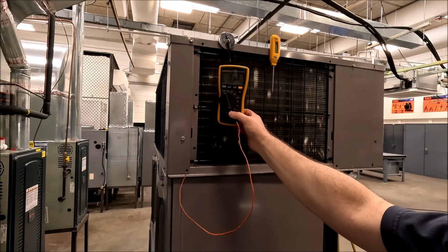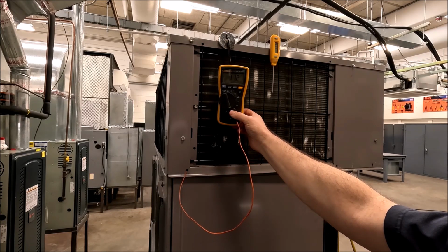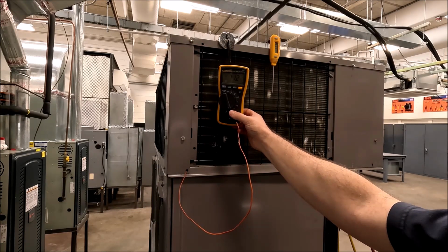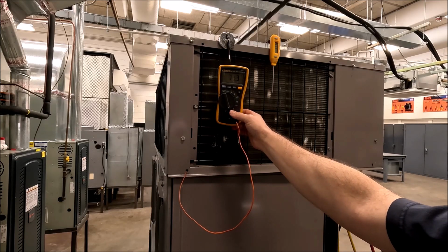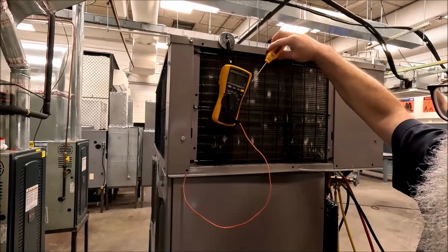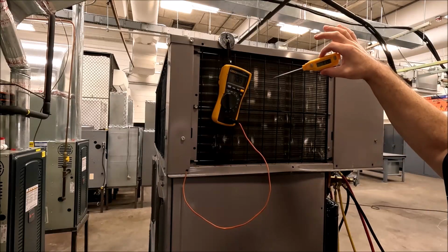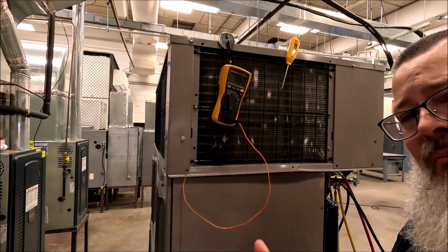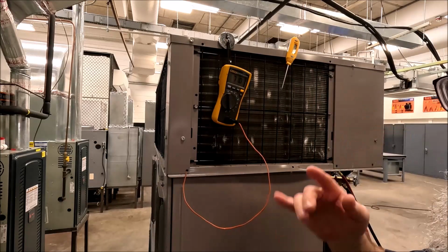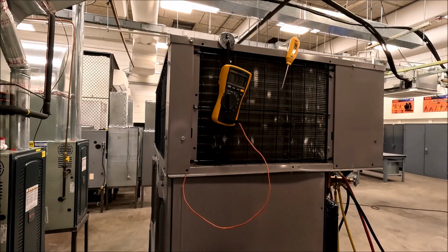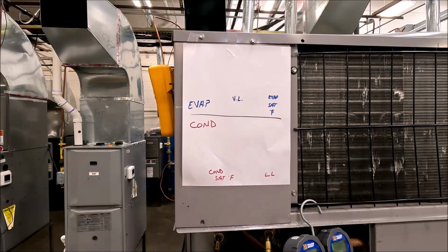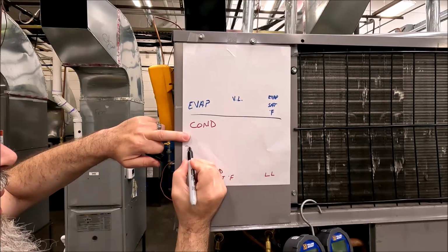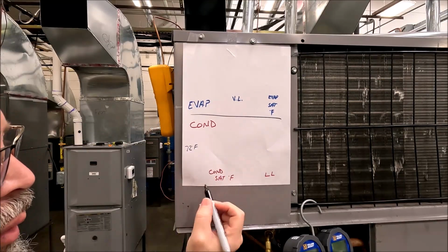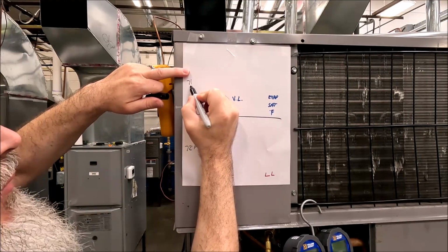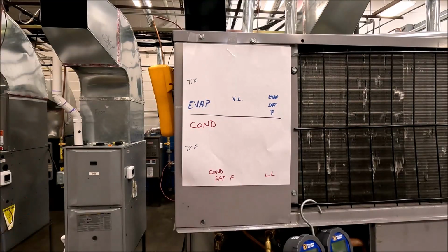And you can see we're about 71, it's going up a little bit, not very fast. So if it evened out at 71.5, that'd be fine. And on the outside, because we're inside, it's going to be about 71.9. They're pretty close. I've got two different brands, two different types, so we'll take it for what it is. So 71 to 72 degrees. All right, so we're going to say it's 72 degrees going in our condenser, and it was about 71 degrees going in our evaporator, all right?